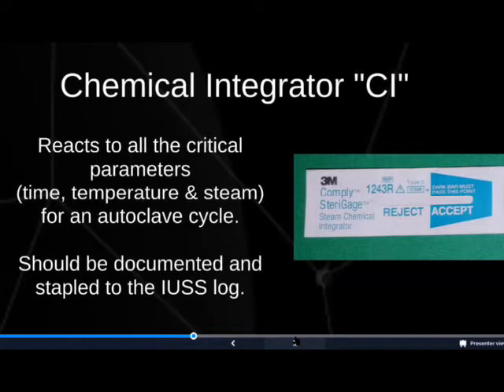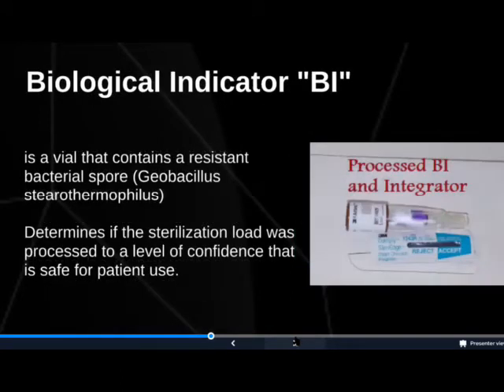So the chemical integrator reacts to all of the critical parameters: time, temperature, steam for an autoclave. It should be documented and stapled to the IUSS log. And I showed you that in the picture before. The biological indicator contains the resistant bacterial spore, Geobacillus stearothermophilus. It determines if the sterilizer load was processed to a level of confidence that is safe for the patient.